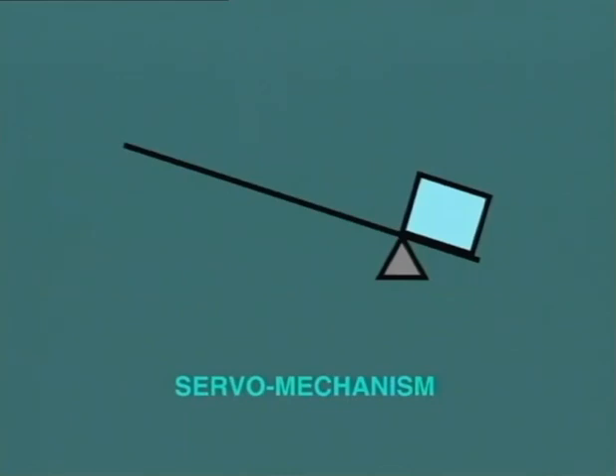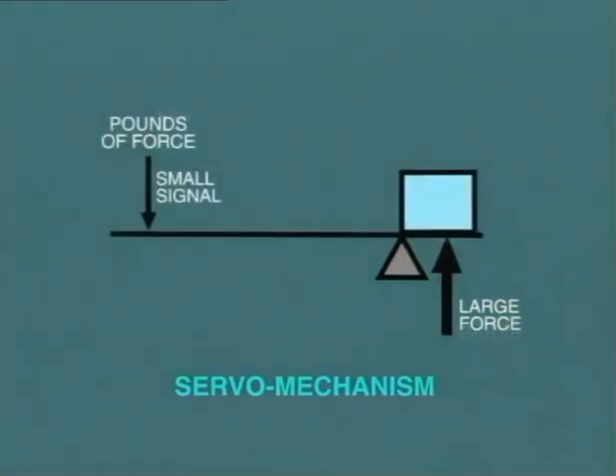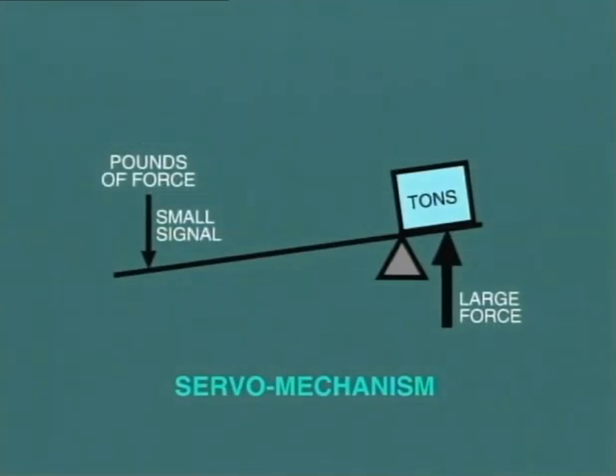Hydraulic oil is employed to provide a relatively large force in response to a small signal from the control system. For example, the servo mechanism that we just mentioned is really a power amplifier that responds to a small movement and force of, say, a few pounds from the governor's system and turns this into a force of several tons to operate the turbine valves against the high-pressure steam.